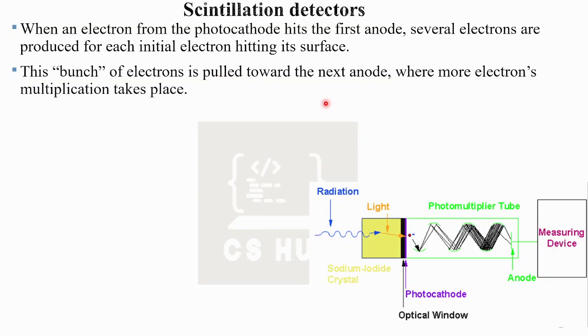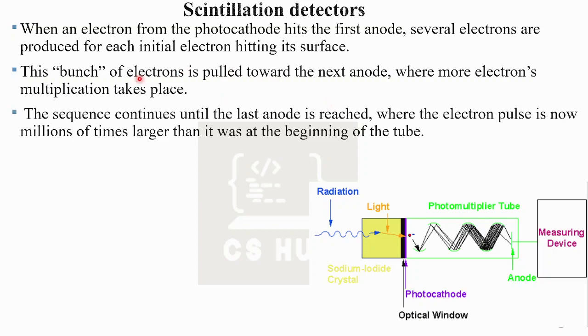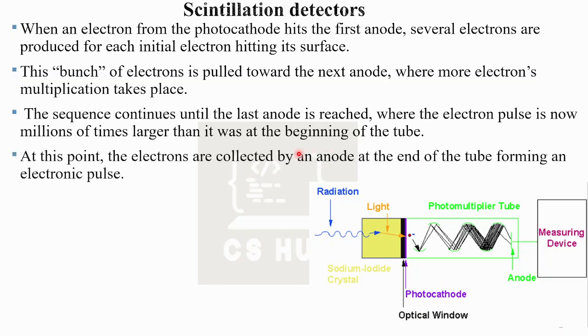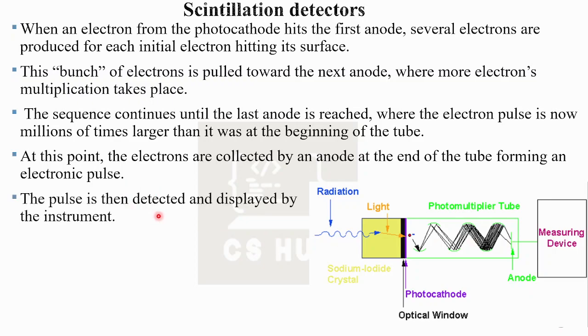This bunch of electrons is pulled towards the next anode where more electron multiplication takes place. The sequence continues until the last anode is reached, where the electron pulse is now millions of times larger than it was at the beginning of the tube. The electrons are collected by an anode at the end of the tube forming an electronic pulse. This pulse is detected and displayed by the measuring device to measure radiation.